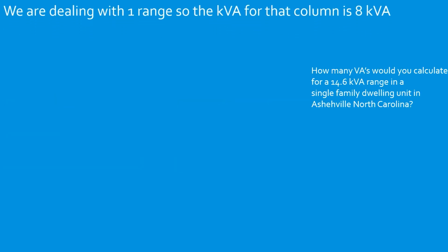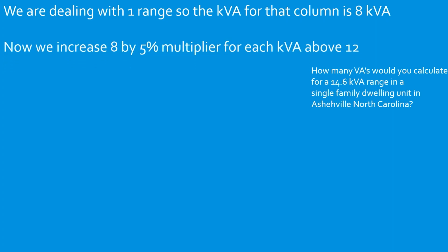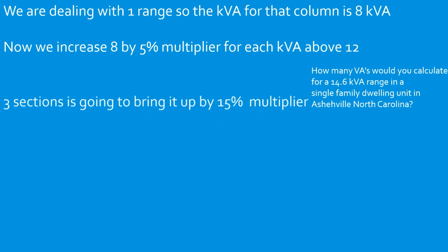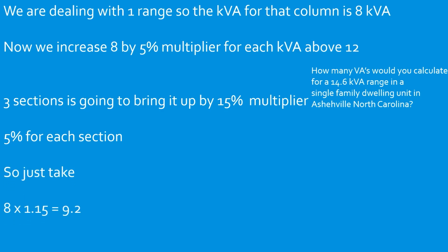Now what we do, we go back and we do our normal steps. We start on the left-hand side for our number of appliances. We come over and we tee off with column C, okay? And we're going to find that 8 kVA is our base. Now we need to increase that by 5% for each kVA above 12. We've already done the math that we are 3, which brings it to 15%.